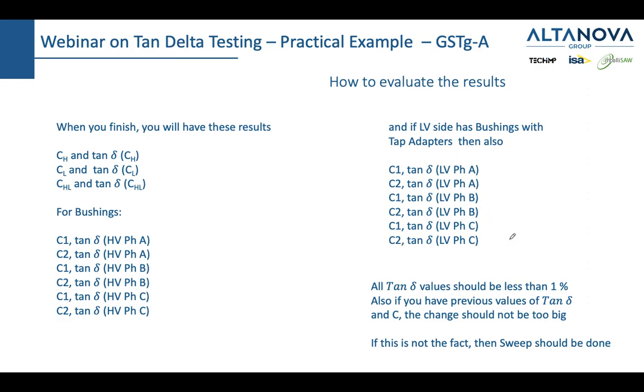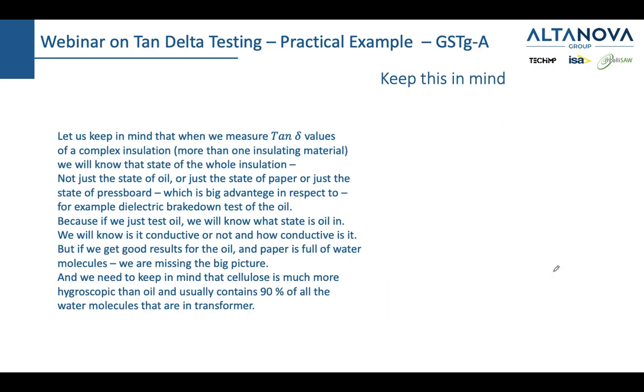And long story short, the easiest way to interpret results is that all tan delta values should be less than 1%. For capacitance, there is no standard. The only thing is that you should have the previous values. And if that value changes more than 7%, this is, again, a value I heard a few years ago, but I haven't found it in any standard, it was more of an empirical value. If the capacitance changes more than 7%, that's a sign for alarm. If you have some tan delta values which are more than 1%, you would do a sweep to get a better view of what's happening. And we are almost done.